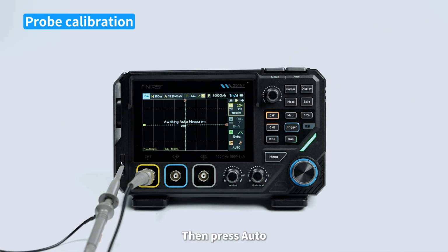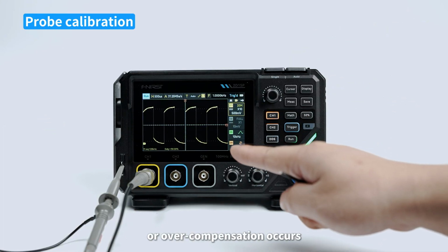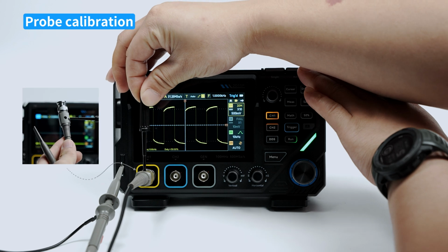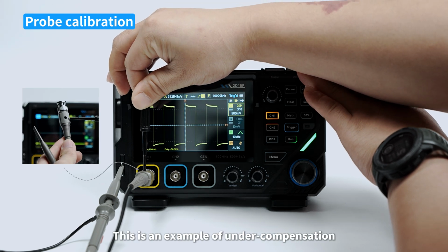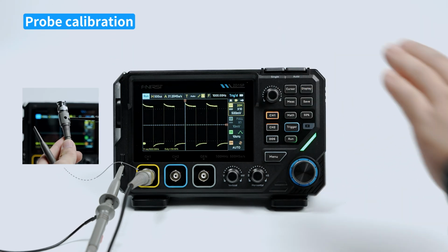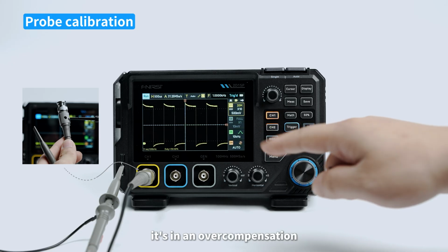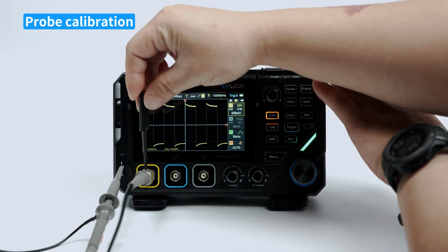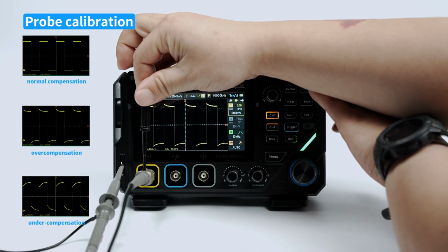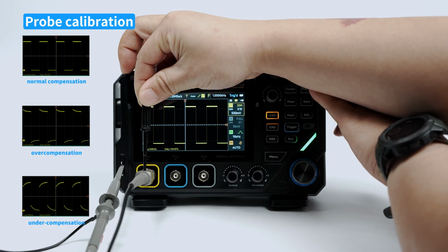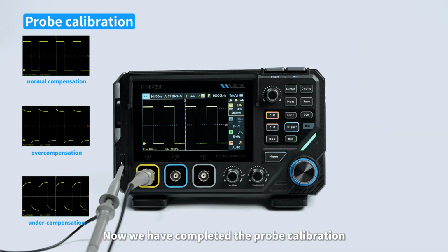Then press auto. If undercompensation or overcompensation occurs, this is an example of undercompensation. Adjust it upwards. In this case, it's in an overcompensation. Adjust it down. Now we have completed the probe calibration.